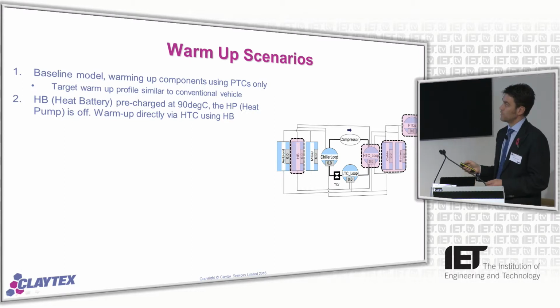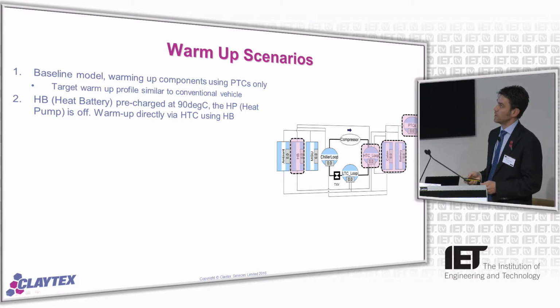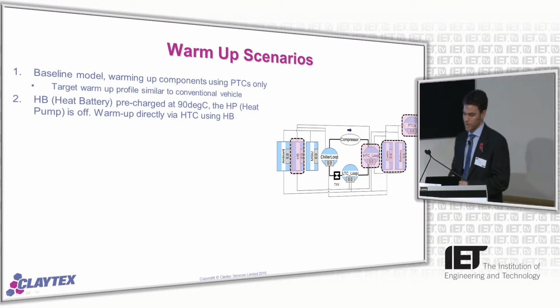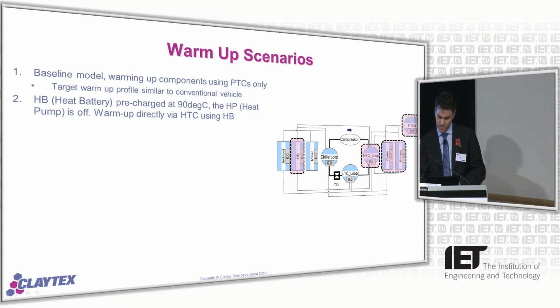The first scenario is to have a pre-charged heat battery which we can connect directly to the high temperature circuits. In this case, we're not using the heat pump - we're transferring heat from the heat battery to the high temperature circuit, which is in turn connected to the cabin and battery. Where we can't fulfill the thermal management requirements, we add additional thermal energy using the PTCs.